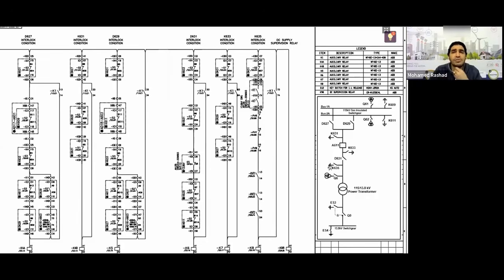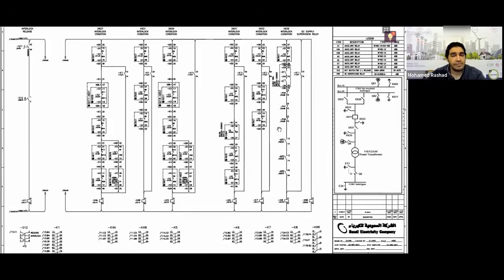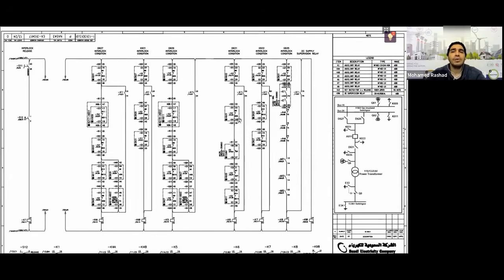Therefore, once the earth switch is closed, if I try to insert the breaker as rack in, I will find the interlock preventing me from doing so. Why? Because the earth switch upstream is closed. Is that clear, guys? This is how my interlocking works.